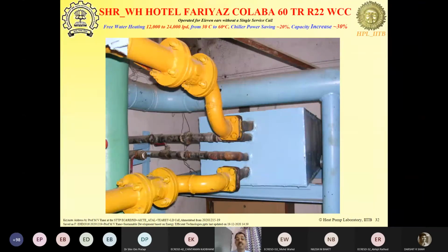My PhD student, Professor Tandle, who worked on this at that time, helped in fabrication of this, got it fabricated. Okay, and in this case, we are generating hot water up to 24,000 liters per day, heating water from 30 to 60 degrees. On the 9-year-old chiller, the chiller power consumption went down by 20%. Okay, and the chiller capacity went up by 30%. Actually, this is not power consumption. Power consumption went up by 10%. COP went up by 20%. So the COP went up by 20% because power consumption increased by 10%, but the cooling capacity increased by 30%.